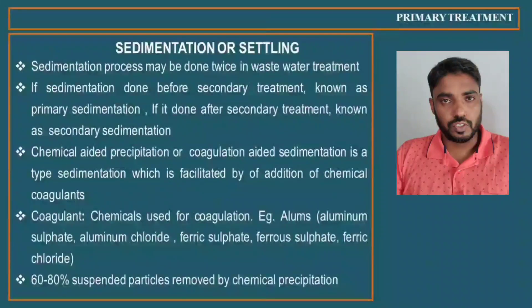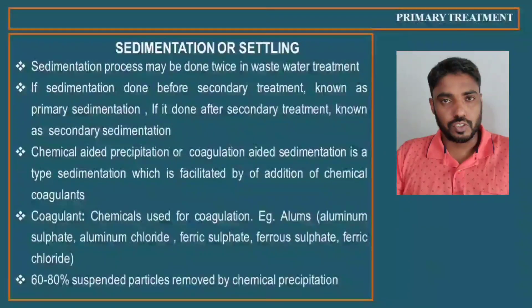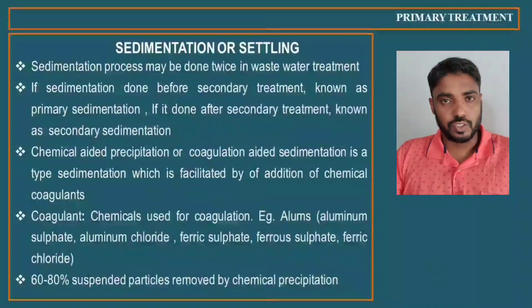When sedimentation of suspended solids is not easy, chemicals called coagulants are used to facilitate the process — this is known as chemical-aided sedimentation or coagulation-aided sedimentation. Commonly used coagulants include aluminum salts such as aluminum sulfate and aluminum chloride, and iron salts such as ferric sulfate, ferrous sulfate, and ferric chloride. Alums are also commonly used. After chemical-aided sedimentation, about 60–80% of suspended particles are removed.